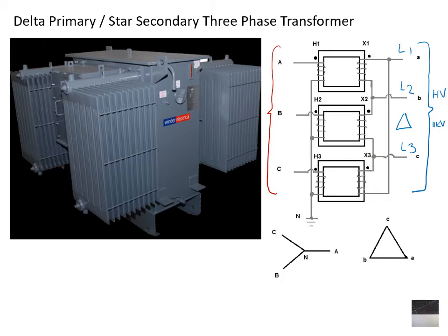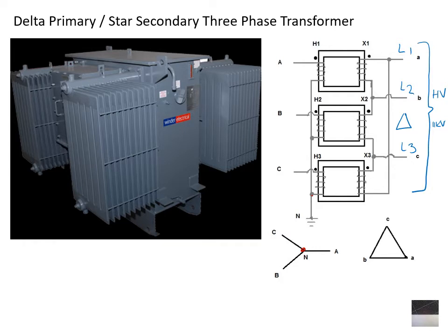On the secondary side is the star connection, giving 400/230 volts. You can tell it's star because all the windings are commonly connected together at a centre point. With a star connection we connect that centre — the neutral point of the star — to earth, which is zero volts. This is done via large earth electrodes, which sets the middle of the transformer at zero volts.